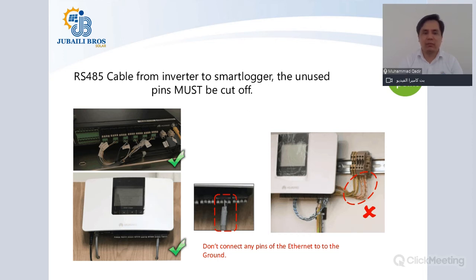For the RS485 cable from inverter to smart logger, the unused pins must be cut off. You have two options for connecting the RS485 cable with our 36 kilowatt and above size solar inverters. There is an Ethernet port which you can use, and there is also an RS485 port. The Ethernet port can also be used to take out RS485 communication data using an Ethernet cable.